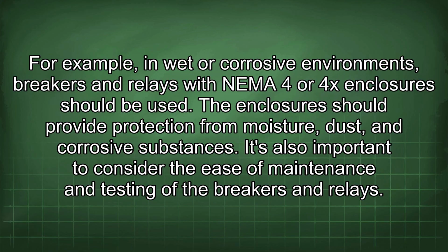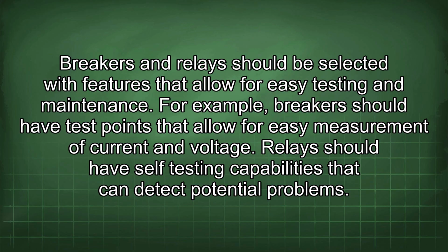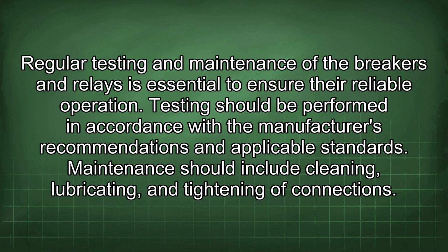The enclosures should provide protection from moisture, dust, and corrosive substances. It's also important to consider the ease of maintenance and testing of the breakers and relays. Breakers and relays should be selected with features that allow for easy testing and maintenance. For example, breakers should have test points that allow for easy measurement of current and voltage. Relays should have self-testing capabilities that can detect potential problems. Regular testing and maintenance of the breakers and relays is essential to ensure their reliable operation. Testing should be performed in accordance with the manufacturer's recommendations and applicable standards. Maintenance should include cleaning, lubricating, and tightening of connections.